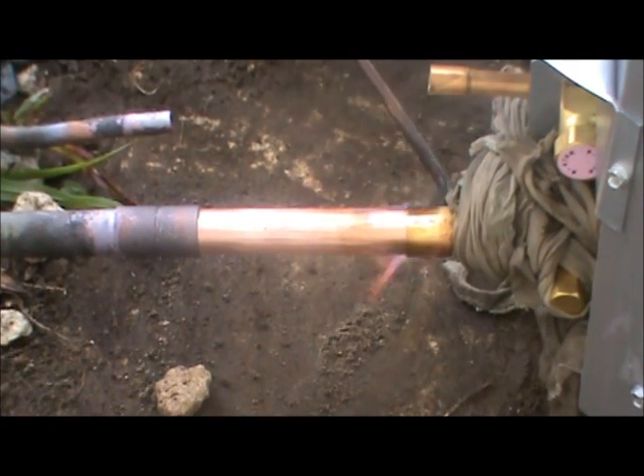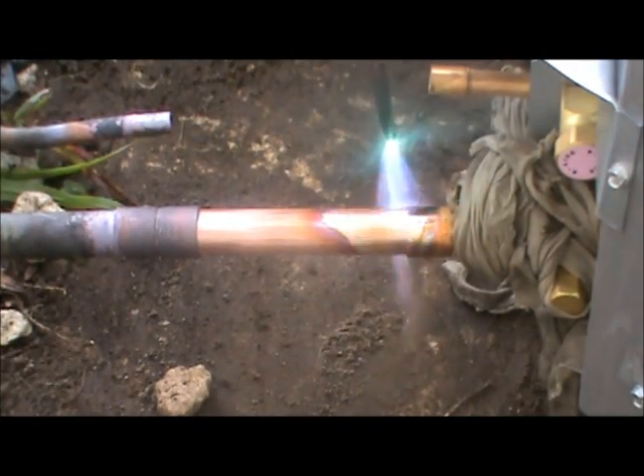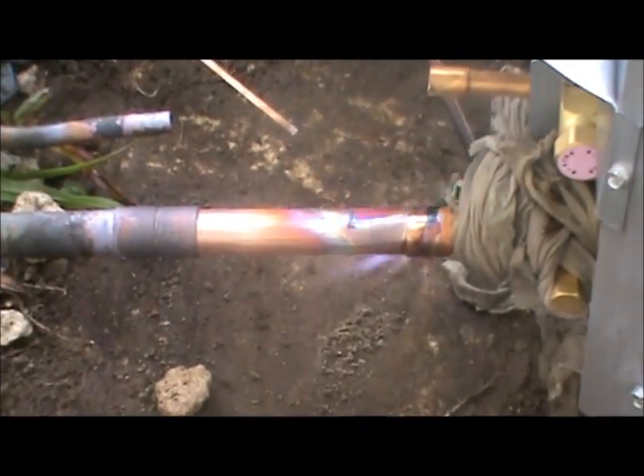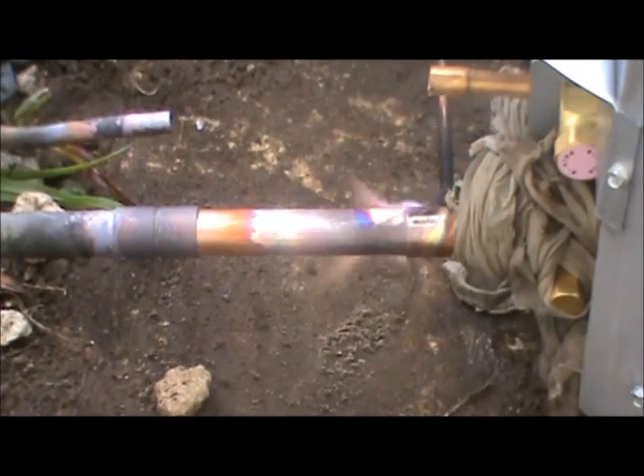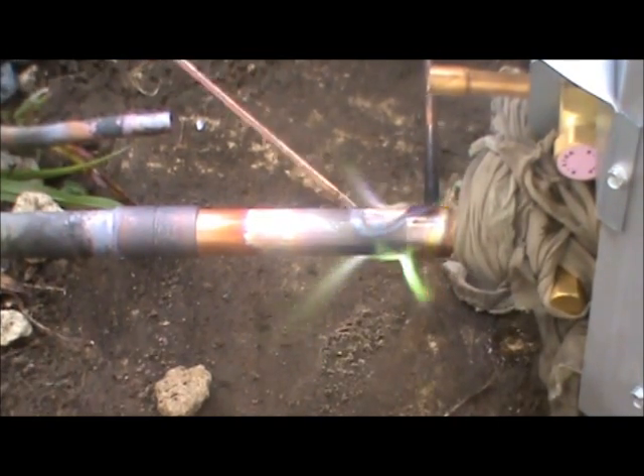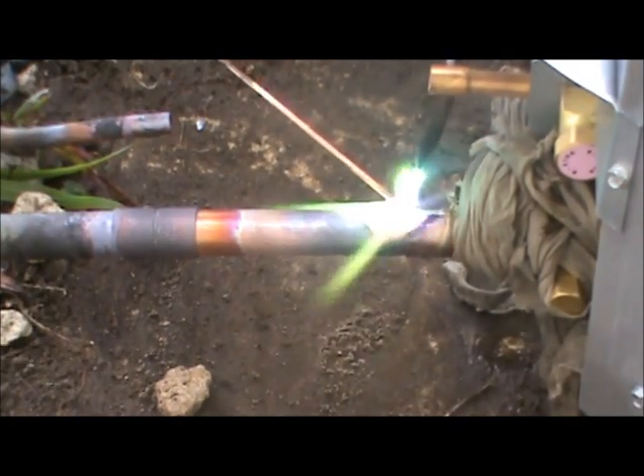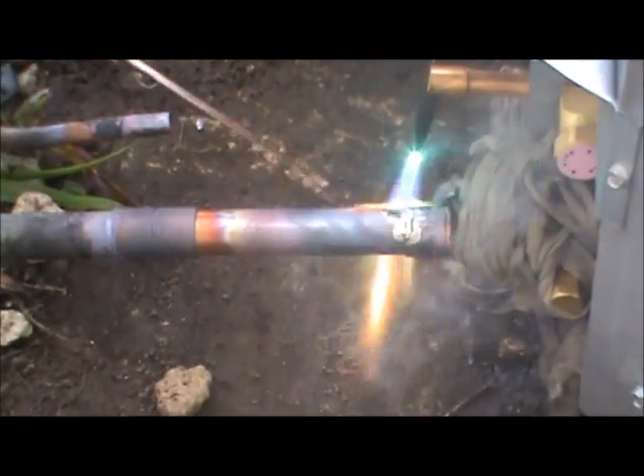And this is where it takes patience. I want to get that joint heated up, trying to keep it pointed away from the valve. You see the flame start to turn green? You know that your joint is hot enough. You want to heat that joint up, but not the Sil-Fos itself — it will just burn off the tip.